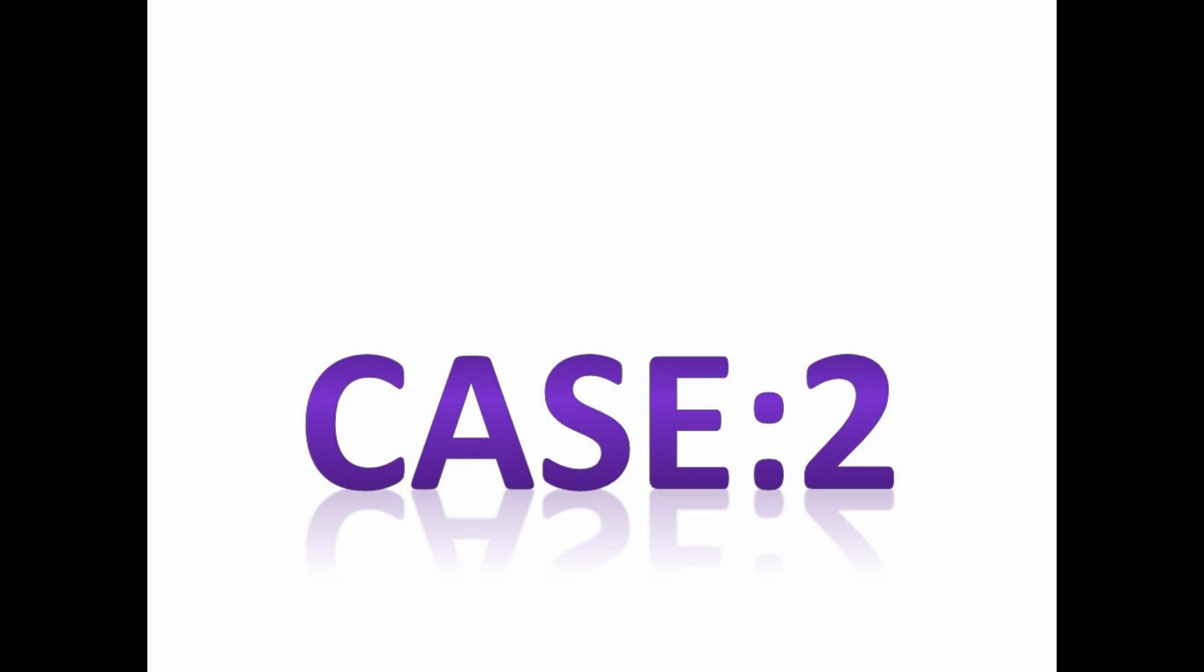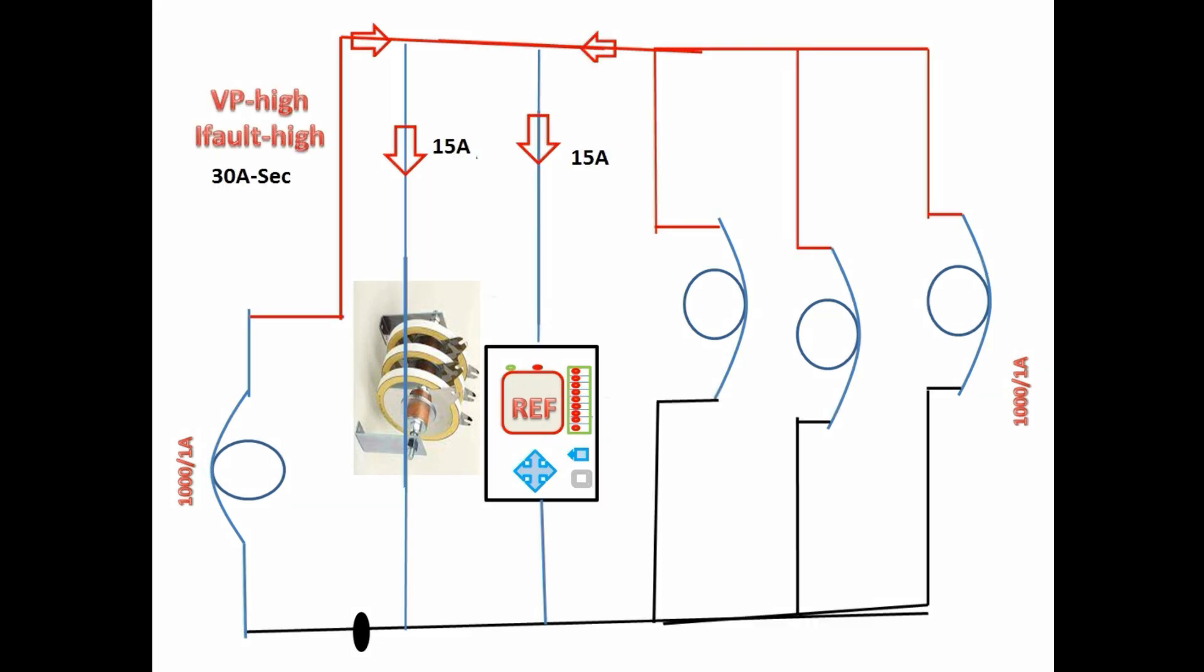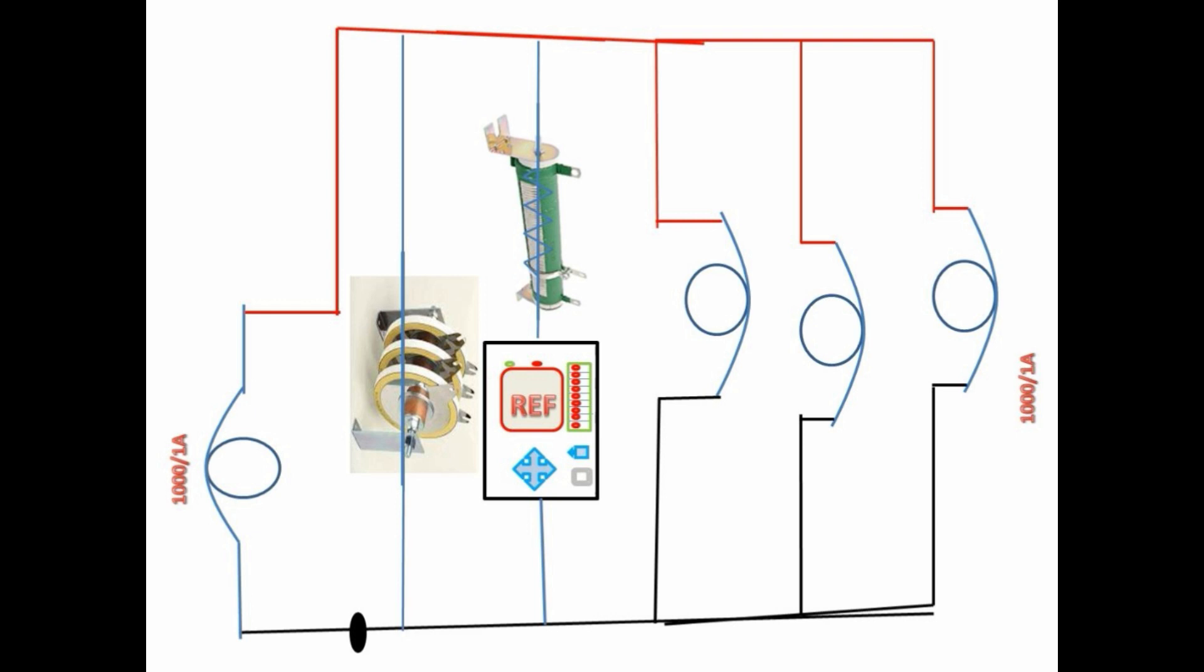On case 2, we consider this time we are not having a RS resistor. In this case also we are going to consider very very high fault. So the secondary will be high. It will be more than 20 amps in secondary. And we have a peak voltage. When we have a peak voltage, then metrosil resistor will start to conduct current. Even though it start to conduct current, the relay CT is also very low resistor path. So both will share the current which may lead the relay to get damaged due to this high current. We may think when we have high current, better to isolate the relay from the fault current. If we do like this, then the relay will not issue TRIP command to the breaker. By this we came to know RS resistor is also very important. We have to protect relay and equipment by issuing TRIP from the relay.